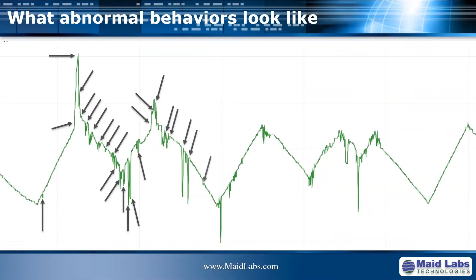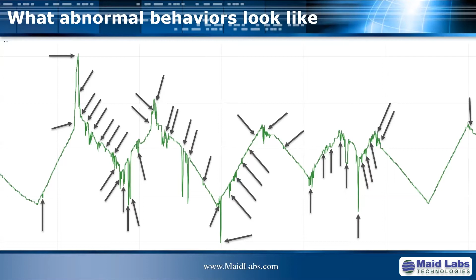You can see abnormal behaviors here, I'll show a few examples. These are real, they came from a lift station with a SCADA system that did not report alarms because the events were just too short to create major problems. But there really was a level sensor issue.